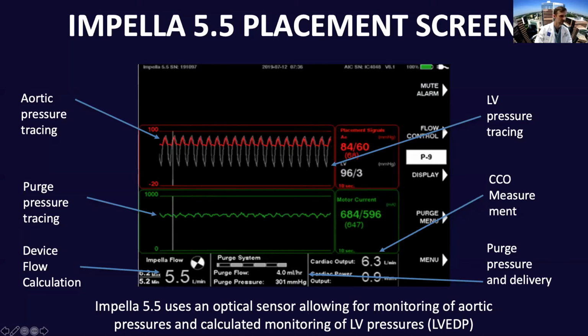We should note that these pressures are calculated pressures. They're not directly measured, such as those that are in the 2.5 device that have a direct channel that measures. This is through a calculation and deduction of a pressure difference as well as a difference in the motor current that enables the engineers to actually provide an algorithm and deduct the pressure in the aorta and the left ventricle.